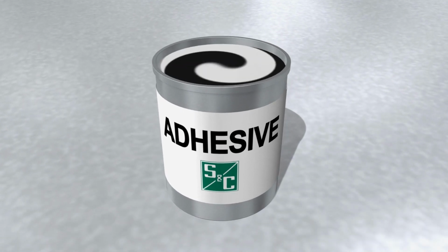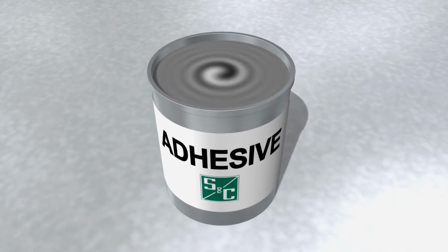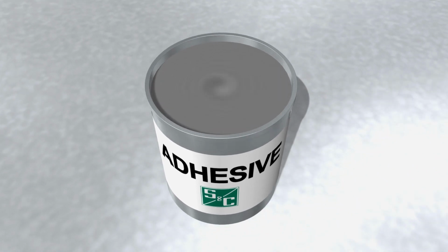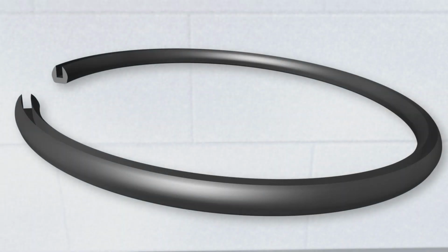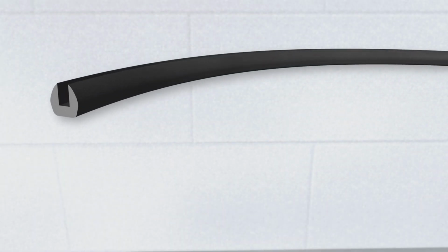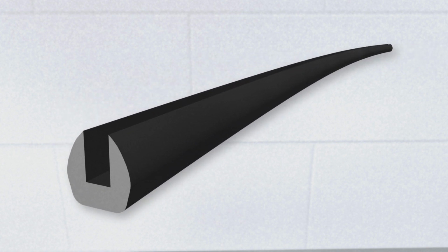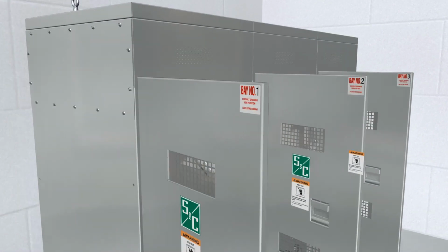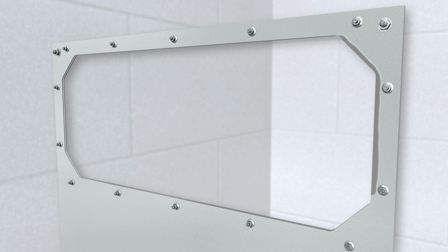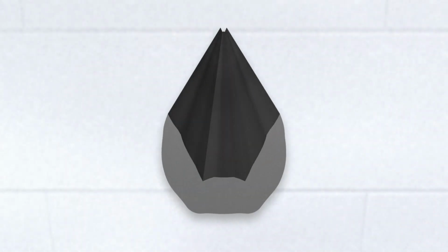B. Stir the special adhesive provided until the color is the same throughout. Cement the channel gasket in place with the adhesive. Apply this adhesive evenly to the 2 sides and top of the bus opening flange in both bays and to all inside surfaces of the channel gasket.